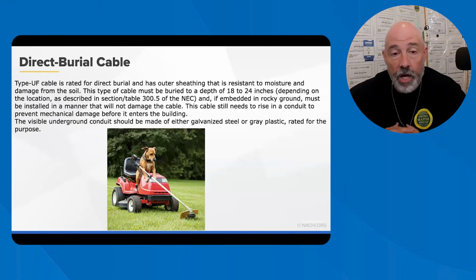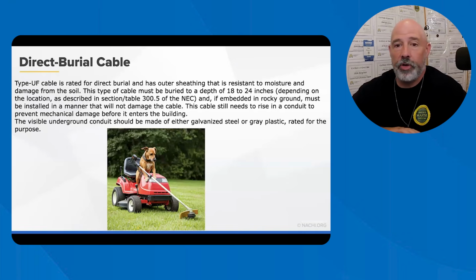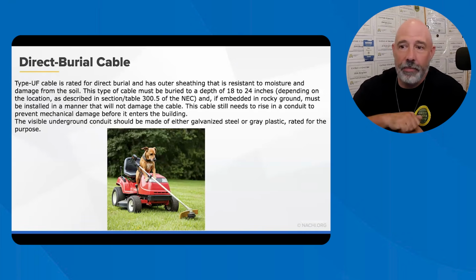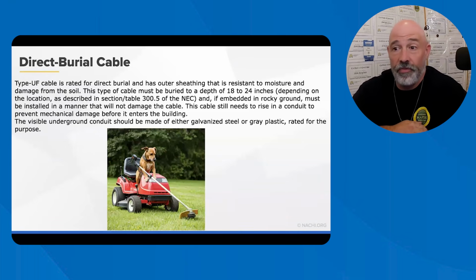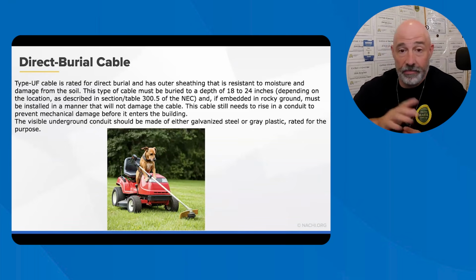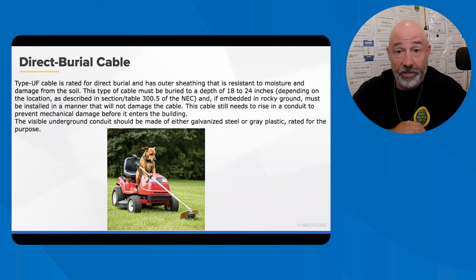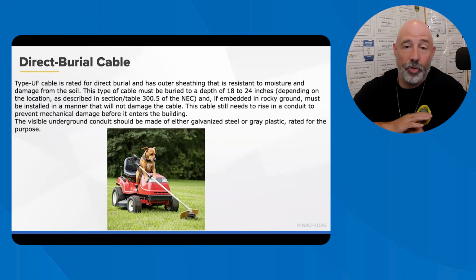Underground connectors, the UF cable is approved for direct burial and is designed to resist moisture and soil conditions. It is typically buried about 18 to 24 inches deep, depending on the jurisdiction, of course, and installation requirements. Even direct buried cable should be protected by conduit where it emerges from the ground and enters into that house. Visible underground conduit should be made of galvanized metal or gray electrical PVC.